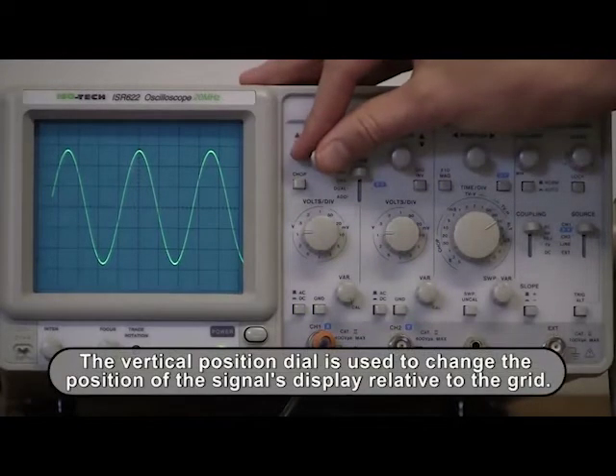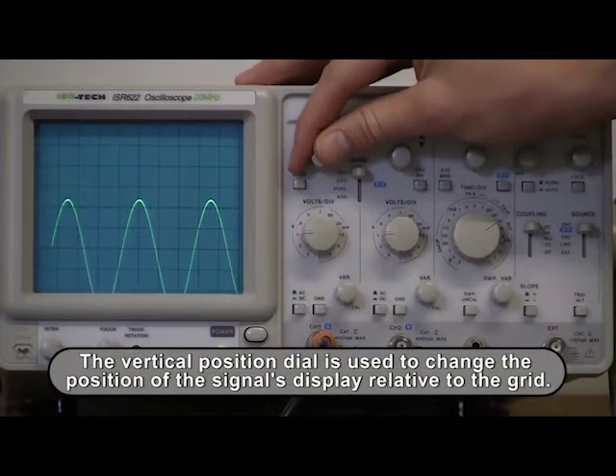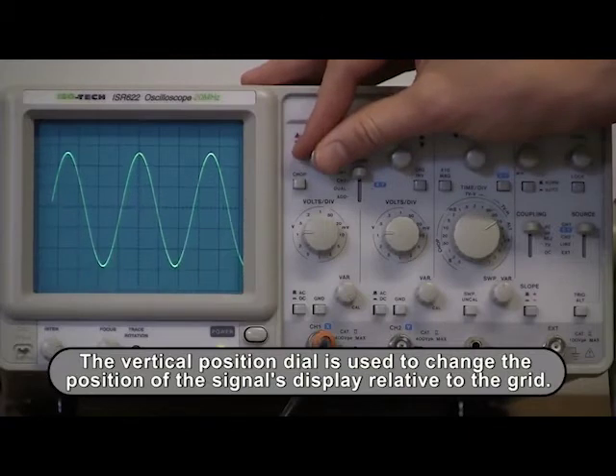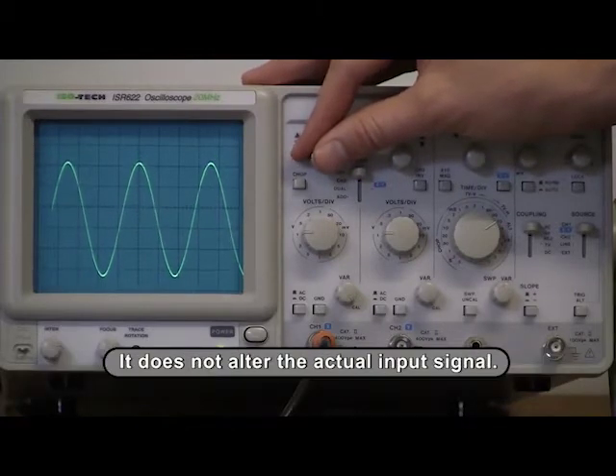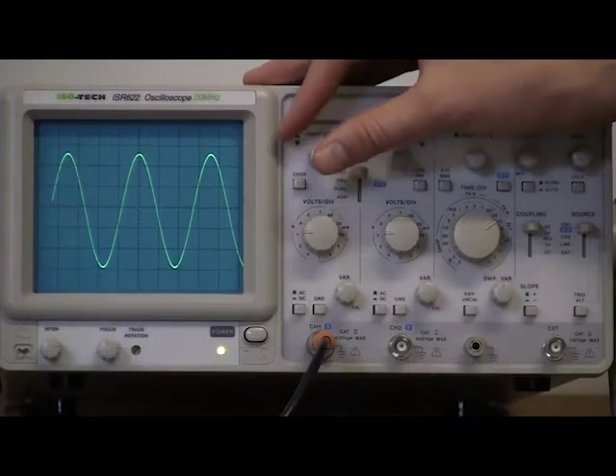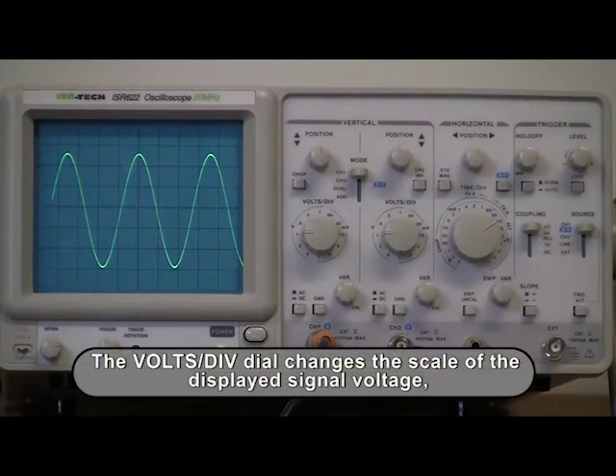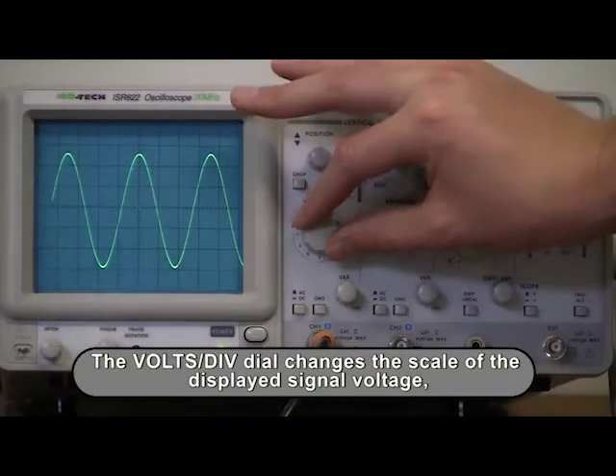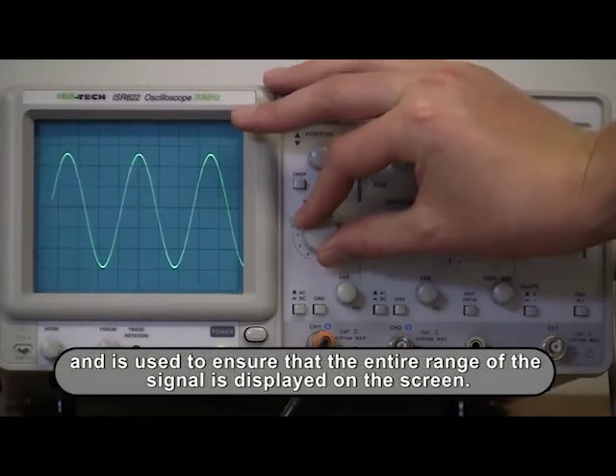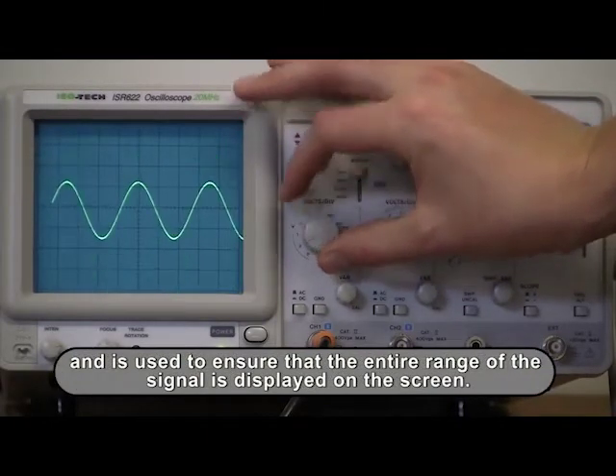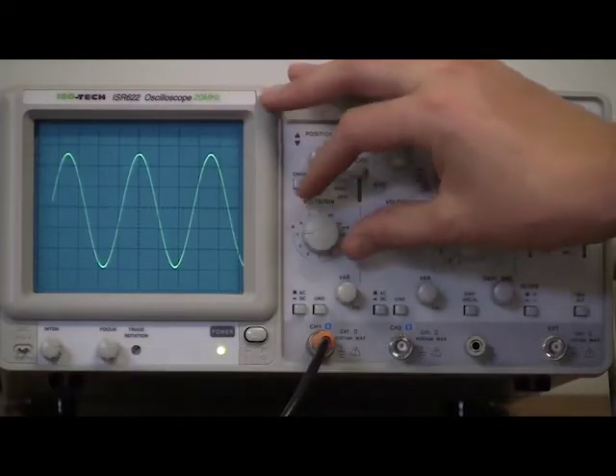The vertical position dial is used to change the position of the signal's display relative to the grid. It does not alter the actual input signal. The volt per division dial changes the scale of the displayed signal voltage and can be used to ensure that the entire range of the signal is displayed on the screen.